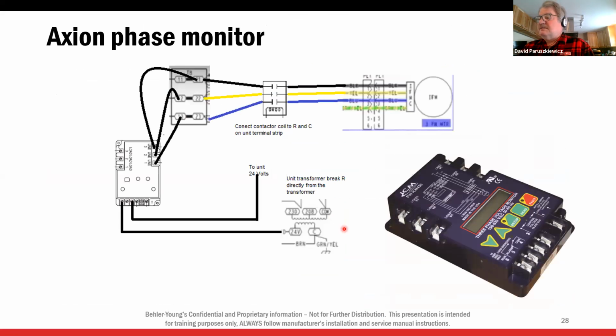Now, because this motor has power to it all the time, if you have high voltage, and I've seen high voltage, this unit is designed for 187 to 253. It's 230 plus or minus 10%. I've been in areas where I've seen 255 at times, 256. If we have high voltage like that, we need to put some type of surge protection, phase protection on these motors. But to just simply put it on the unit, it'll keep the compressor from coming on. It's not going to protect this motor. So to protect the motor, we need to put a contactor in line so that if this phase voltage monitor trips, it kills power to the whole unit or to the motor to protect it.